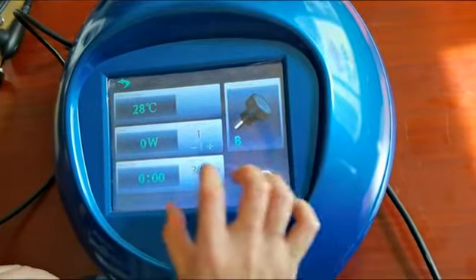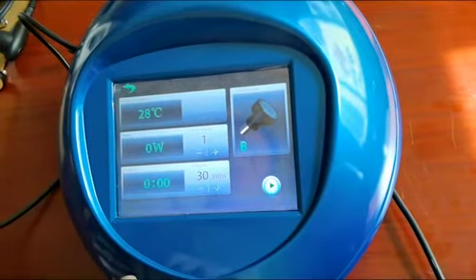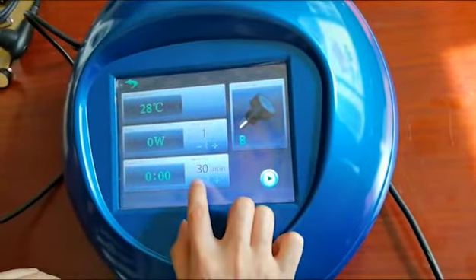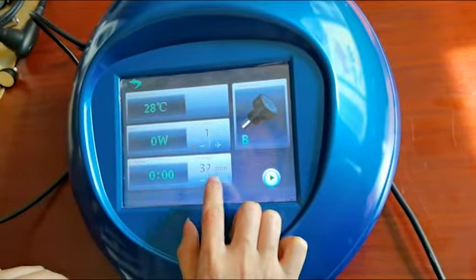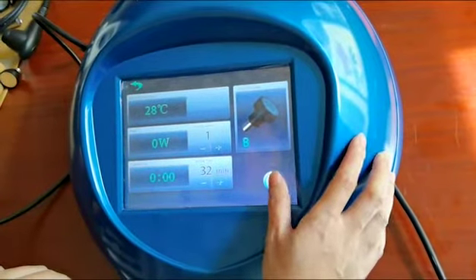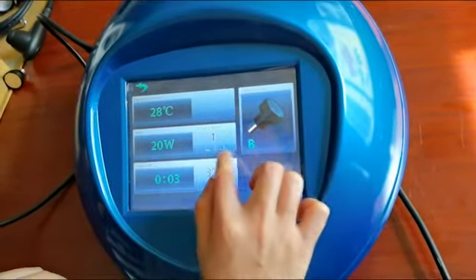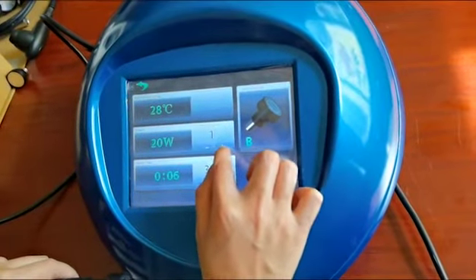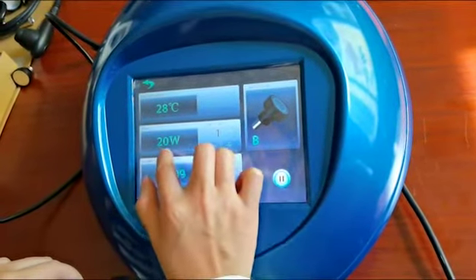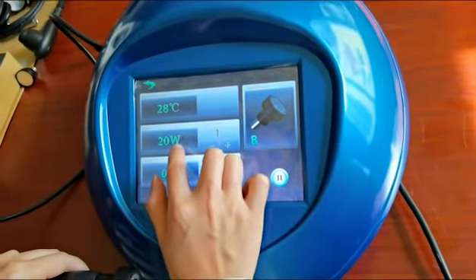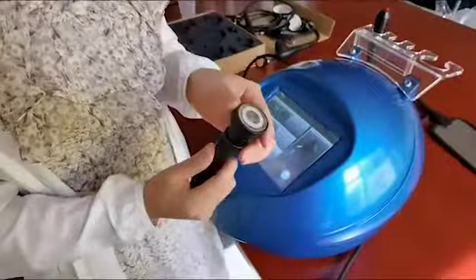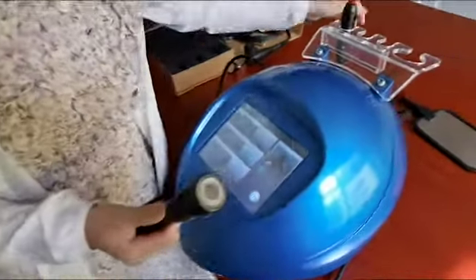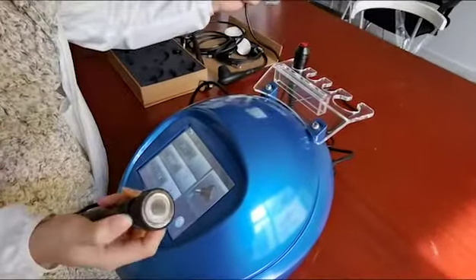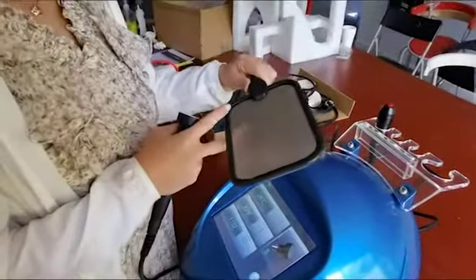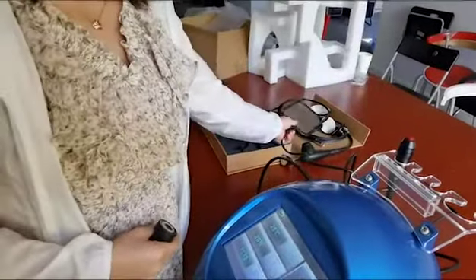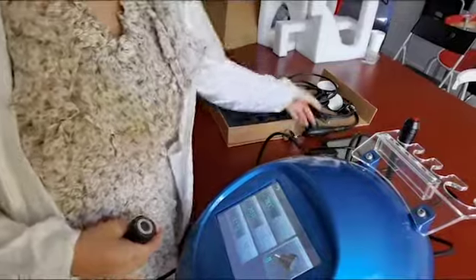You go to the parameter setting interface, and you can set the treatment time. For the power, when you press the start button, you can increase or decrease the setting. We suggest starting from the lowest, 20 watts. This is the Monopolar RF cartridge. For this machine, only this cartridge doesn't need the electric pad. The electric pad is for the other Monopolar cartridges.